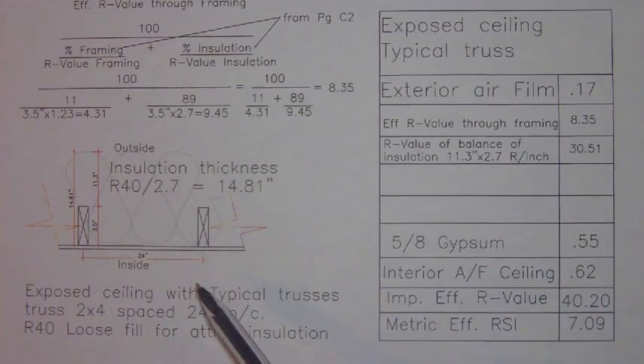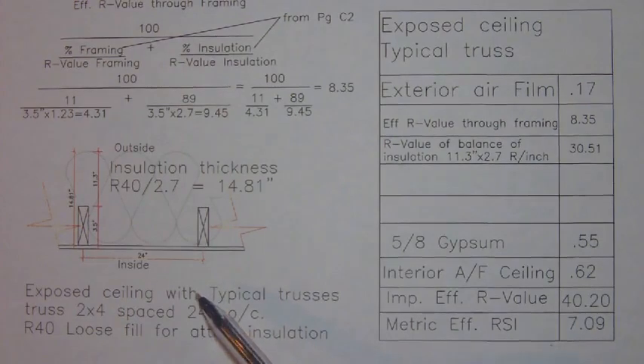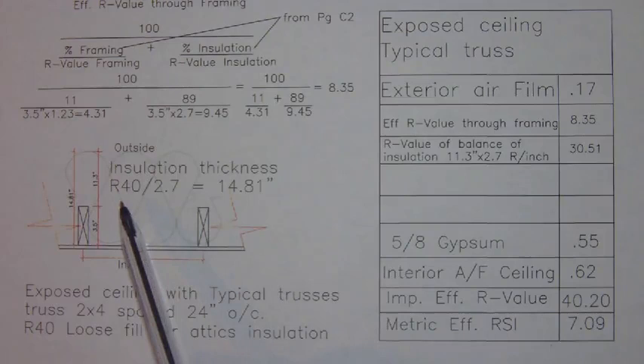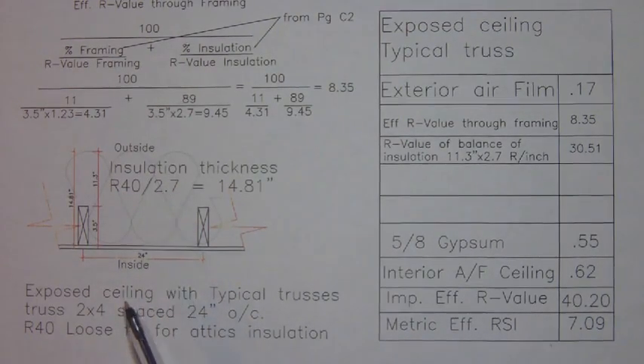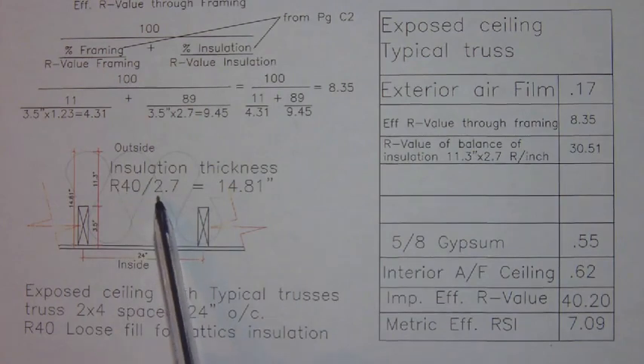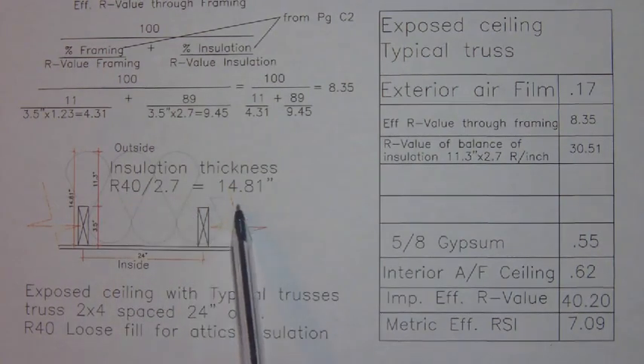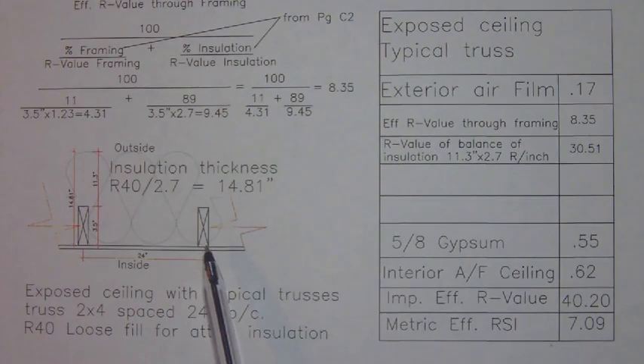Now we know we want to have R40 insulation, but how thick does that actually have to be? So all you need to do is divide R40 by the R-value per inch, so R40 divided by R2.7 per inch, and we come up with 14.81 inches, or probably 15 inches of insulation. Loose fill for attics would give us R40.